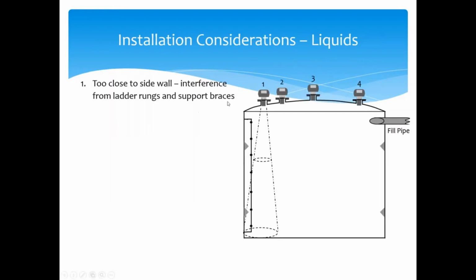For transducer location number 1, this is a question we've already had answered so far. But if you're too close to the sidewall here, or in this case, this ladder or fixed obstruction, that's going to cause signal return or interference for us, which will affect our level measurement. Now, I will point out that with something like a ladder or any sort of fixed obstruction inside a vessel, we could do mapping and ignore that fixed obstruction. I'll have a slide a little bit later on that discusses that.